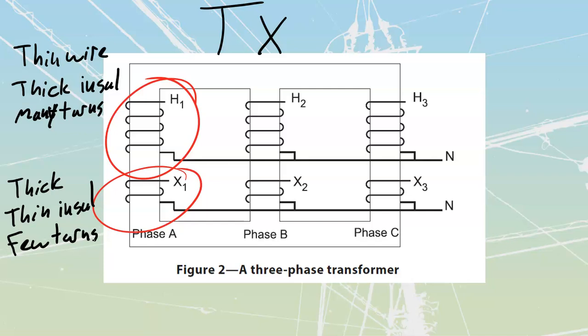Anytime you open up a transformer, you should be able to identify these. The other way to identify transformer high and low voltage is off of what we call our standardized markings. These markings have a prefix, the first letter, which is either H, standing for high voltage, or X, standing for low voltage.